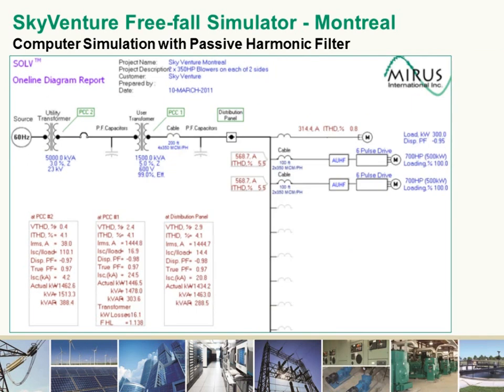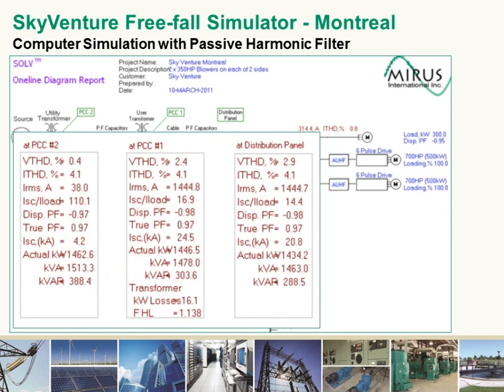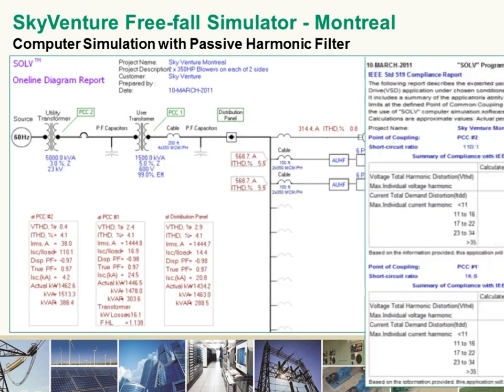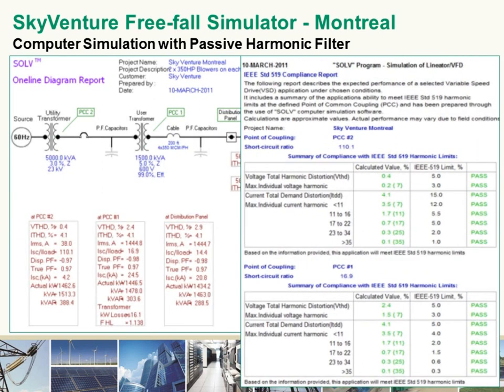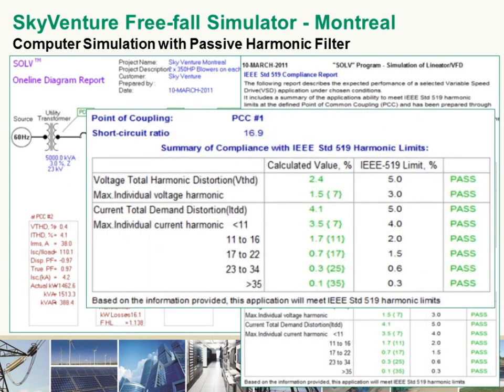And by applying Mirus' passive harmonic filters, known as the Lineator AUHF, the computer simulations show that IEEE Standard 519 limits can be met. The application was simple in that two Lineator filters were used to each supply two of the 350 horsepower VFDs. So again, we have a 700 horsepower total load and a Lineator filter ahead of the 6-pulse VFD. We now see that current distortion dropped to 4.1%, voltage distortion went down to 2.9. Our IEEE 519 compliance report shows that we passed both in voltage distortion and in current distortion. In other applications since this Montreal project, similar skydiving simulators, we've used single Lineator filters to supply all 4 fans.